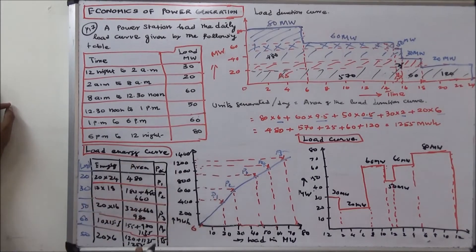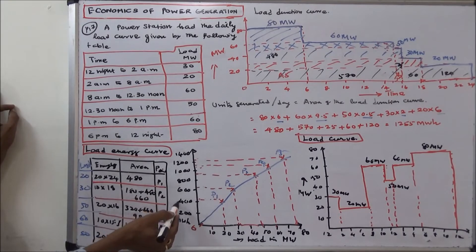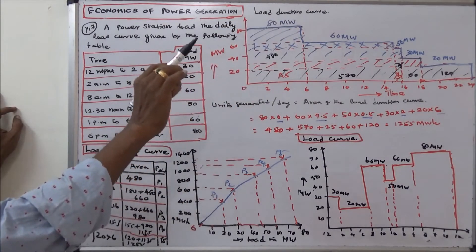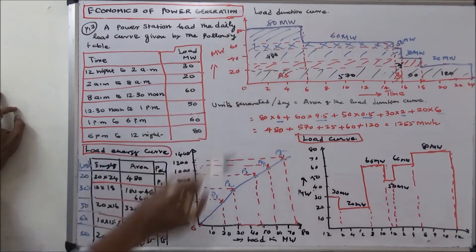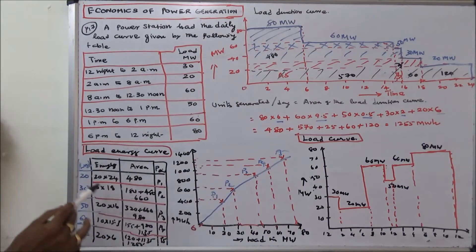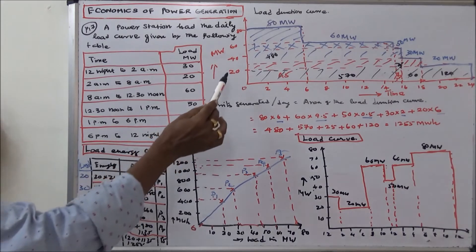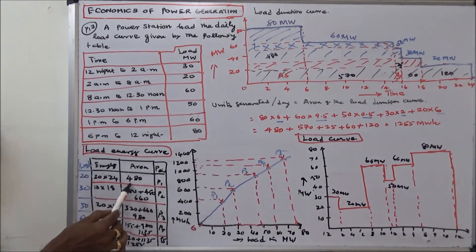Next we draw the load energy curve. X-axis is load in megawatts, Y-axis is energy in megawatt hours. From the load duration curve, we calculate five areas: A1, A2, A3, A4, A5. At load 20 MW: energy = 20×24 = 480 MWh — this is point P1. For area A2: 10×18 = 180; 180 + 480 = 660 — this is point P2 at 30 MW.